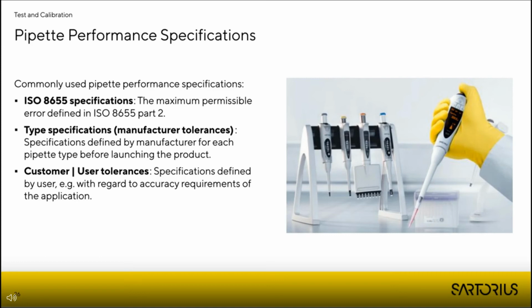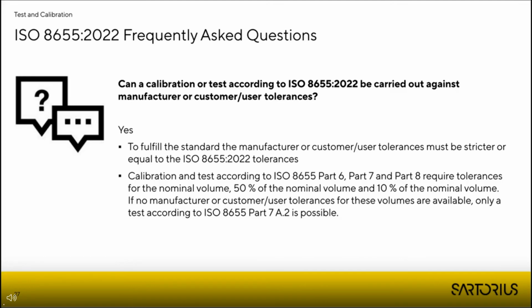The question, of course, is now: when following the new ISO, is it still possible to test the pipette against manufacturer and customer tolerances, or does the calibration need to be performed always against the ISO tolerances? To fulfill the ISO standard, a test against manufacturer and user tolerances is possible, but these specifications need to be stricter or equal to the ISO specs. If they are wider, the confirmation of the ISO standard cannot be given.